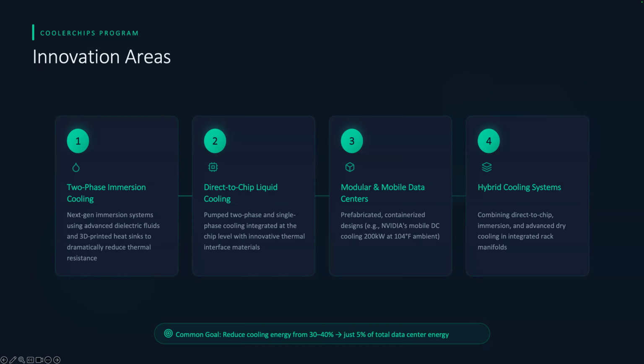They take their waste heat off the data center and then boost it with heat pumps, and that looks very promising, especially if your heat pump is efficient. So it's viable, but the devil's in the details — if you've got a lot of piping distance, you lose a certain amount of degrees as it moves, and there's just the cost of that much piping.